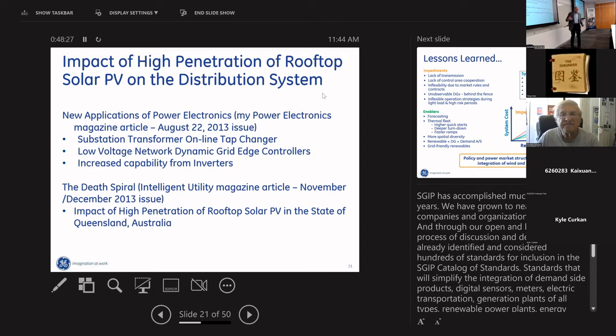Then there are smart inverters, with more functionality and more external control capability. Remember, an inverter is a good VAR source, and the higher the penetration of distributed generation, the more we can use inverters for VAR support on the distribution system instead of installing as many cap banks. We've done a lot of studies on the trade-off between needing cap banks and increasing penetration of distributed generation. So the future grid is much more volatile as distributed generation penetration grows.